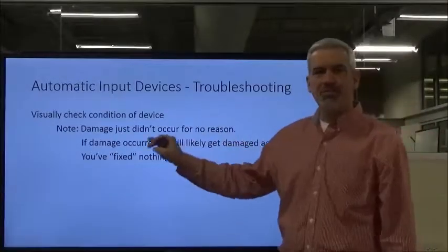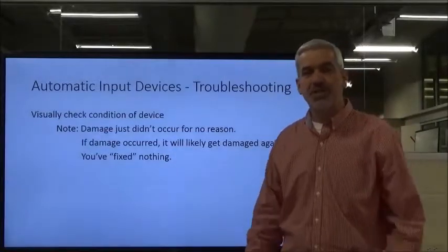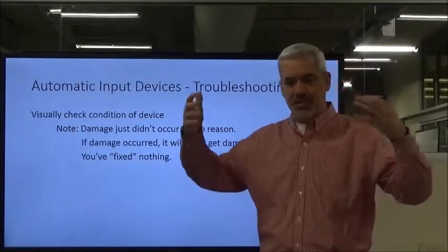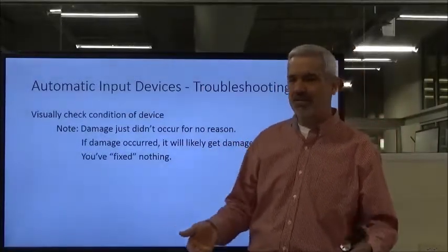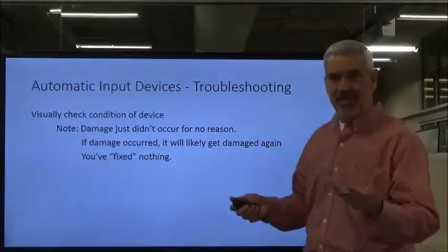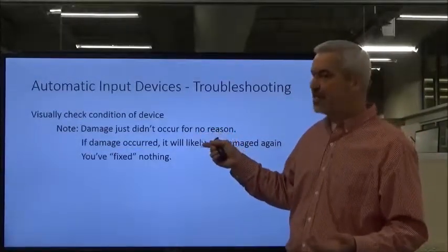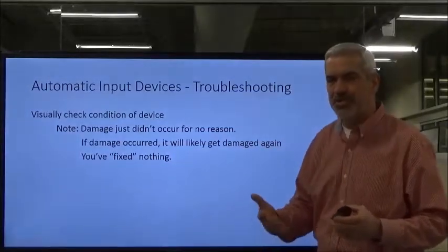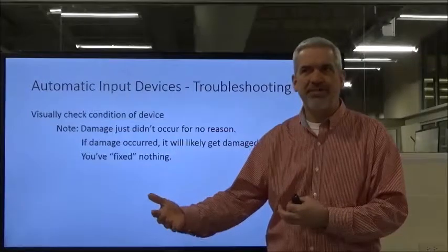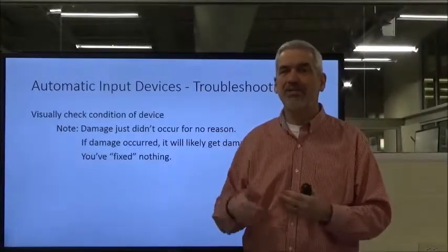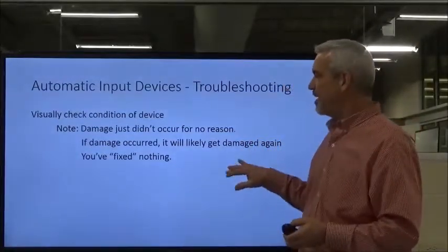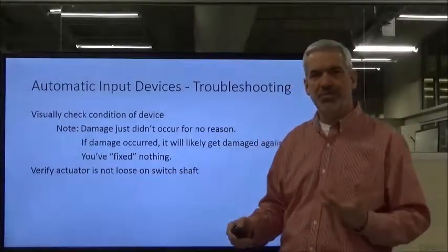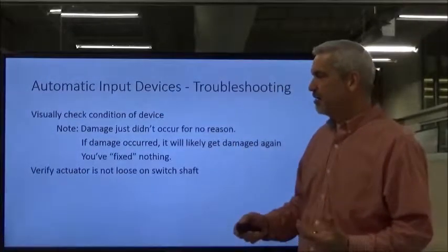You're going to need some form of pressure to make that contact close. If you don't have that, is your air compressor on? Is your line even hooked up to your pressure switch? Is a valve shut off that goes to this pressure switch? That's what we're teaching the whole system here. It's not just electrical. You're going to have to look and say, is my hydraulic pump running? If my hydraulic pump's running, then I've got another problem. And it has nothing to do with the pressure switch. So my point is just be very methodical as you go through this. Try not to jump around too much. When you go up to a device, visually check it out. There's always a good chance. I saw so much in industry, switches and things run over by fork trucks, products dropping and crushing things. It doesn't take a meter and a schematic to figure out, there's my problem.